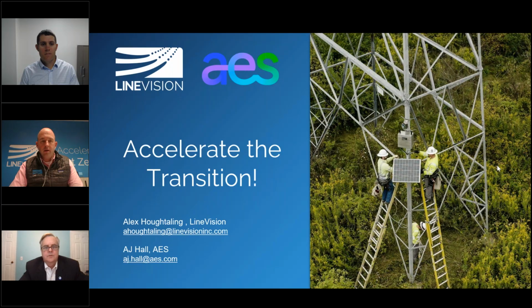Well, in the case of National Grid, the case study I showed, that was the average. In AJ's cases, I think it was between 22 and 50%. A lot of it has to do with the current assumptions going into it. So for example, when you're using static assumptions in your equation, depending on how optimistic you are about wind speed, that's going to have an impact on the capacity gain.